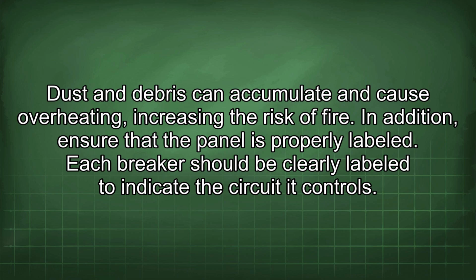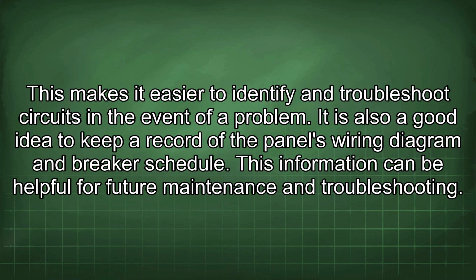In addition, ensure that the panel is properly labeled. Each breaker should be clearly labeled to indicate the circuit it controls. This makes it easier to identify and troubleshoot circuits in the event of a problem. It is also a good idea to keep a record of the panel's wiring diagram and breaker schedule. This information can be helpful for future maintenance and troubleshooting.